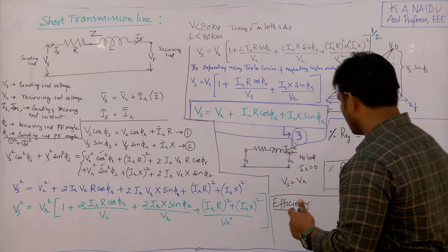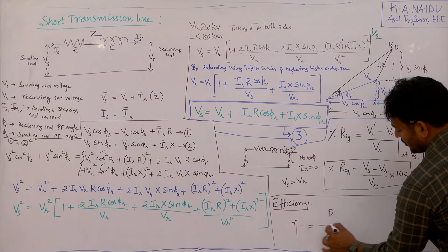Generally the transmission lines are 3-phase transmission lines. Therefore efficiency can be written as equal to, suppose P is the power that is delivered at the receiving end, and then P by, there are 3 lines, and the total current flowing is IR. The total current that is flowing through this R is IR, which is same as IS, that is equal to, let us say, I at full load. This is at full load. So I square R. If you want percentage, simply multiply with 100. So here VR is receiving end voltage, that is at full load, or you can also call it as rated value, rated voltage.